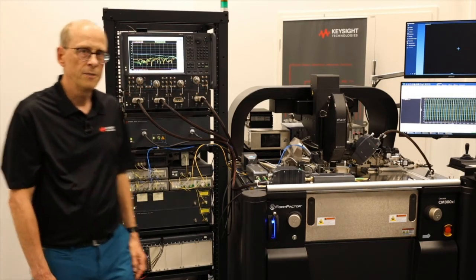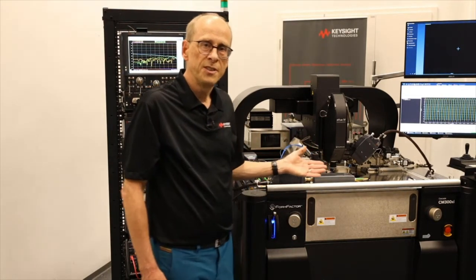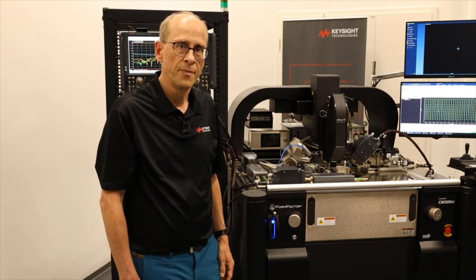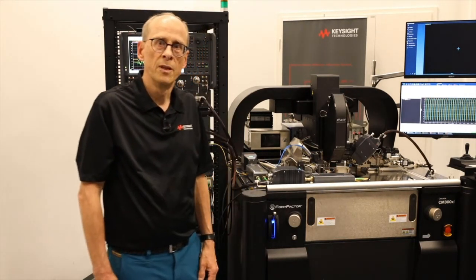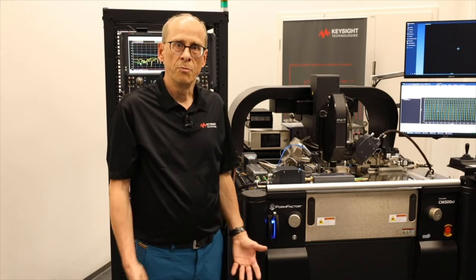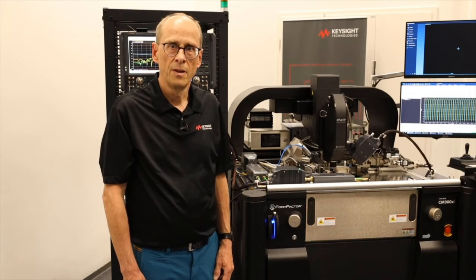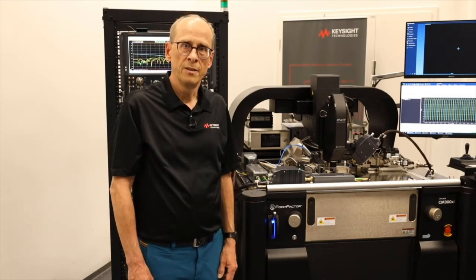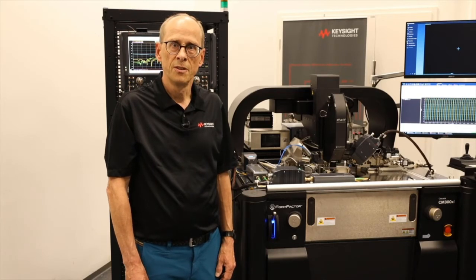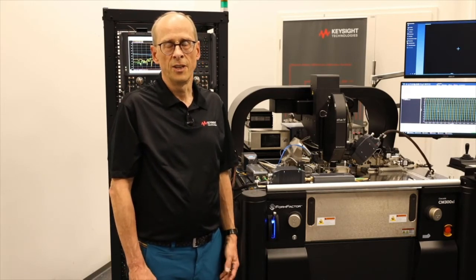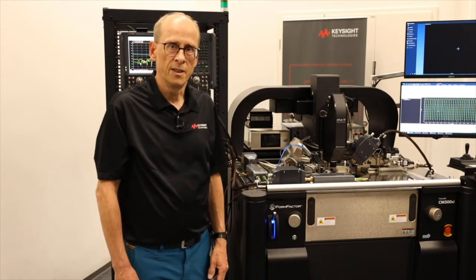For probing, we have the form factor probe station CM300XI. This probe station allows you to perform electro-optic or pure optical measurements on wafers or on singulated dies. Optical probing is with fiber arrays or single fibers, which allow to be connected from either the east side or the west side on a wafer or a die.